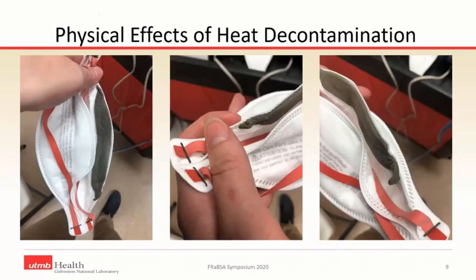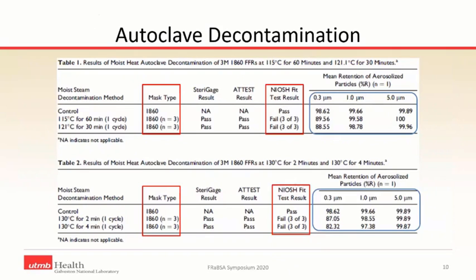Then you can also see some damage from heat, especially when we're doing the 130 degrees Celsius. You can see the foam, the neoprene seal near the nose, getting damaged during the decontamination process. As a result, and this is one of the tables published in the article, you can see that for the 1860s we did three masks for 60 minutes, at 115 and 121 degrees for 60 and 30 minutes. Even though the steri-gauge passed and the test passed, they failed to pass the NIOSH test, or the fit test.